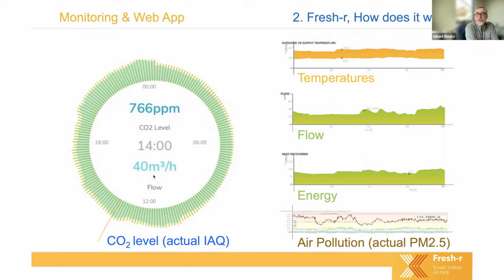And then the last thing, because we get these optical laser sensors, it'll monitor PM 2.5, and it'll actually go down to PM 1. So there are data points, if we step back and look at the cloud interface for building management level, which can be accessed by the occupant level also with different tiers that we can allow. We can see temperatures, flow, humidity, relative humidity, PM 2.5, PM 1, all instantly, ongoing 24/7. And essentially this is a very stable condition right now because that circle is relatively round. I've seen buildings where something happens and there's a whole bunch of PM 2.5 or a whole bunch of humidity, and the circle starts getting different colors and oblong because all these factors start moving away from a norm.